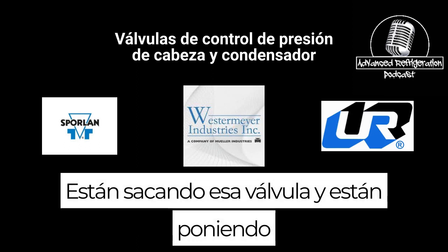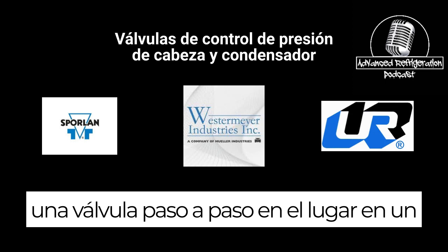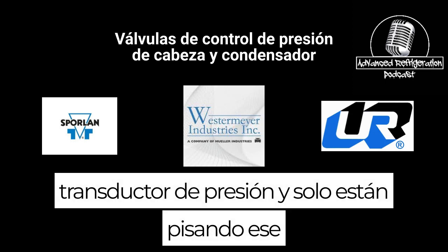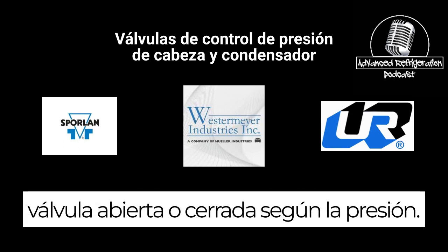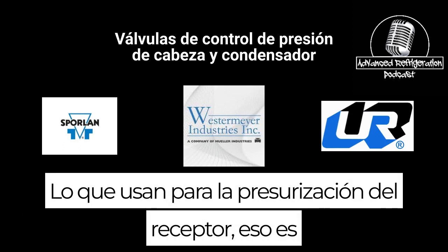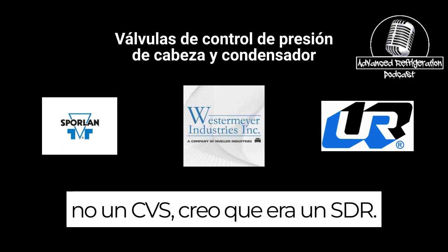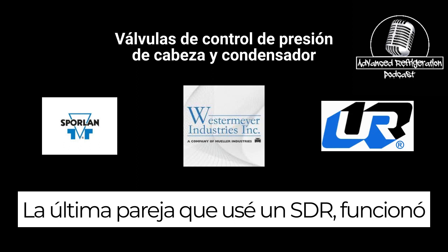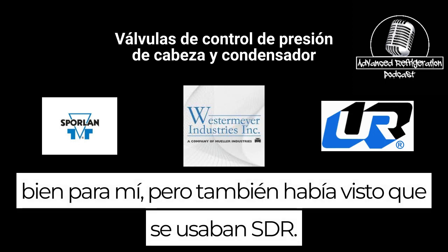They're taking that valve out and they're putting a stepper valve in the spot and a pressure transducer. And they're just stepping that valve open or closed based on pressure. Right, and then what valve would they use for the receiver pressurization? That's not a CDS. I think, what is that, an SDR? Okay. The last couple I did, CDS-4. Didn't have a hard time controlling things. You could use an SDR valve. It's vapor. It worked fine for me. But I've seen SDRs used also.